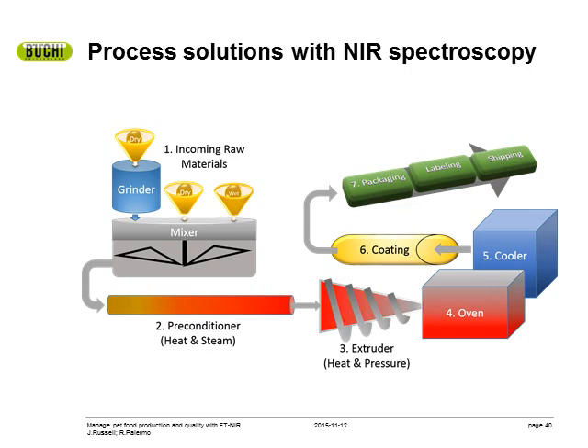And just to reiterate, if it didn't come across in the presentation, the NIRFlex N500 and the NIRMaster are actually an identical spectrometer, and the only difference is the ingress protection offered on the NIRMaster makes it better suited for the production environment, but of course you lose the flexibility of changing the measurement cell. So a NIRFlex N500 with our solids measurement cell is equivalent to the NIRMaster setup, but of course without the ingress protection.